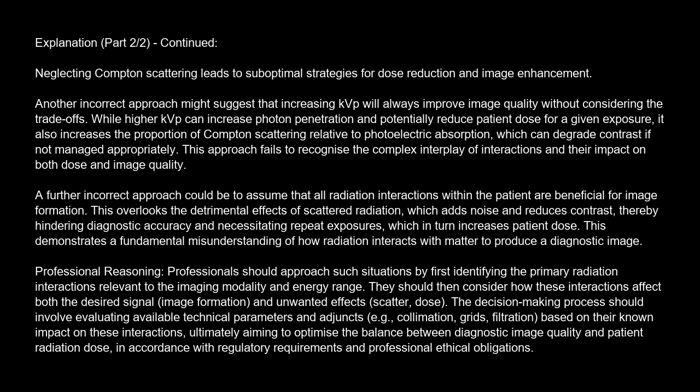Another incorrect approach might suggest that increasing kVp will always improve image quality without considering the trade-offs. While higher kVp can increase photon penetration and potentially reduce patient dose for a given exposure, it also increases the proportion of Compton scattering relative to photoelectric absorption, which can degrade contrast if not managed appropriately. This approach fails to recognize the complex interplay of interactions and their impact on both dose and image quality.